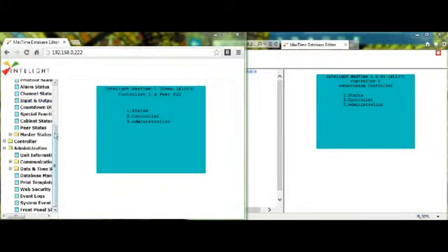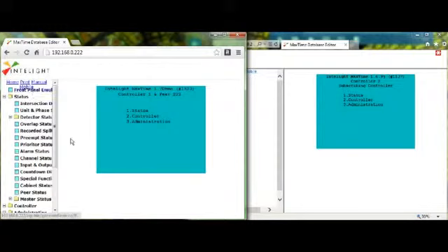Okay, so we're going to start testing this controller. And the first thing we're going to do on the peer controller is to go into statuses. And we're going to go into our vehicle detector status. So we're going to detectors. And here's our vehicle detector status. So I'm going to move the cursor off so you can see it. And when I click my switch, vehicle detector 1 should come on. So click, it's on, click, it's off. So I have to make sure my input is going into the controller and it's seen.